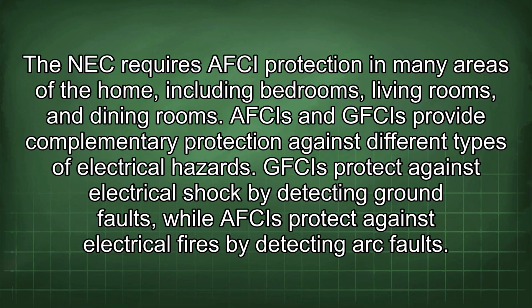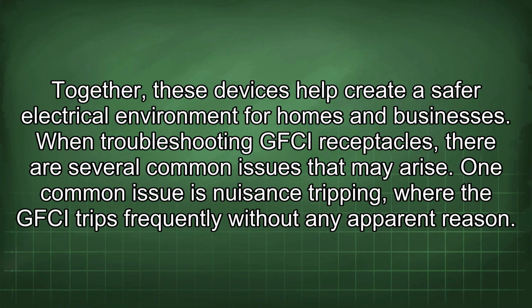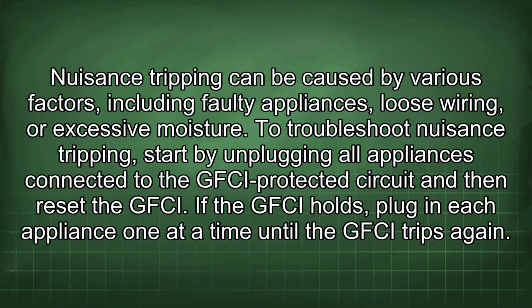AFCIs and GFCIs provide complementary protection against different types of electrical hazards. GFCIs protect against electrical shock by detecting ground faults, while AFCIs protect against electrical fires by detecting arc faults. Together, these devices help create a safer electrical environment for homes and businesses. When troubleshooting GFCI receptacles, there are several common issues that may arise. One common issue is nuisance tripping, where the GFCI trips frequently without any apparent reason. Nuisance tripping can be caused by various factors, including faulty appliances, loose wiring, or excessive moisture.